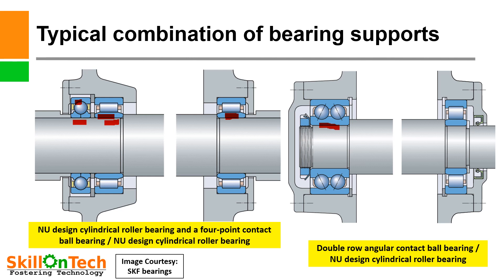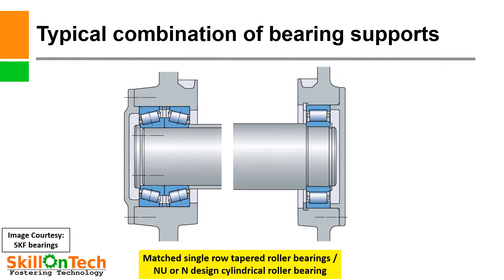A double-row angular contact ball bearing will also provide axial movements, take axial loads, and compensate angular misalignments. The NU design cylindrical roller bearing provides axial movement and takes axial loads. The picture also shows a matched single-row tapered roller bearing combined with a NU or N design cylindrical roller bearing. These are typical combinations of bearing supports provided for locating and non-locating bearings.